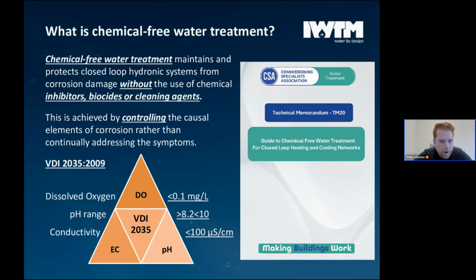And some of the key parameters are dissolved oxygen, which is the #1 cause of corrosion, pH, and conductivity. So to engineer the water to a non-corrosive state, we need to get the dissolved oxygen below 0.1 milligrams per litre. And thinking about your drinking water that you're having right now, it has about 9 to 11 milligrams per litre of oxygen in. So we are reducing that dramatically down to below 0.1. And remember, that's the #1 cause of corrosion. So if you control your dissolved oxygen, you're effectively controlling your corrosion rate.